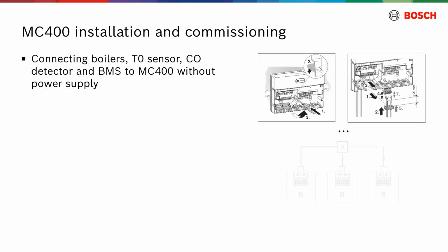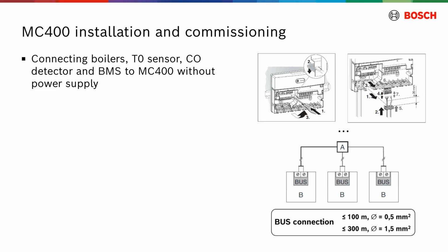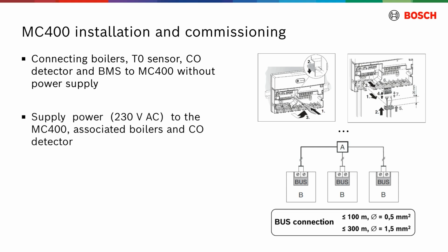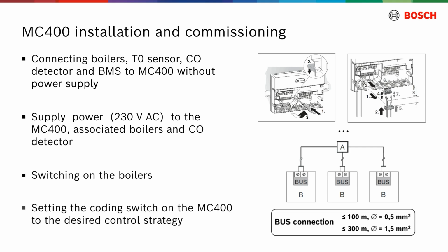Please note, if the maximum cable length of the bus connection between all bus nodes is exceeded, or if there is a ring structure in the bus system, the system cannot be commissioned. Once all connections are properly established, then supply power to the MC400, the designated boilers, and the CO sensor. Afterwards, switch on the boilers. Finally, set the coding switch to the desired control strategy.